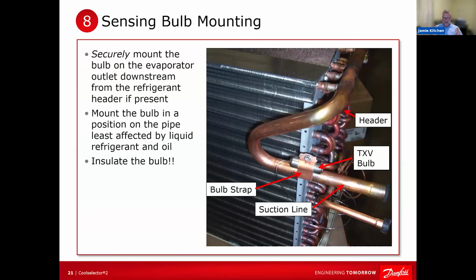If you don't have a bend, put it at 9 or 3 o'clock if you can, right? Somewhere in that area. You're trying to avoid the meniscus at the bottom, which is just the surface tension of the oil that has a natural reaction to go upwards. The smaller the pipe, the farther that oil is going to reach up. But again, use your head, right? Where is that oil going to be sitting? If it's on the bottom of the pipe, don't put it there.